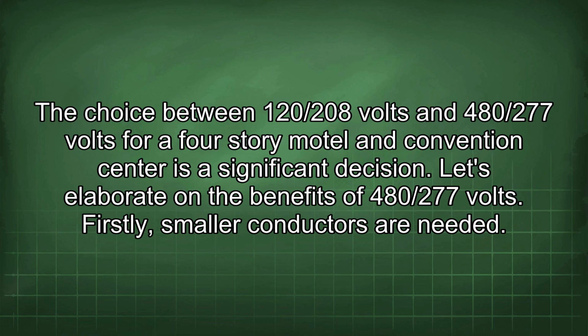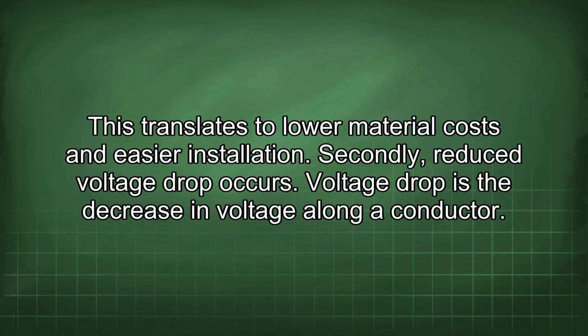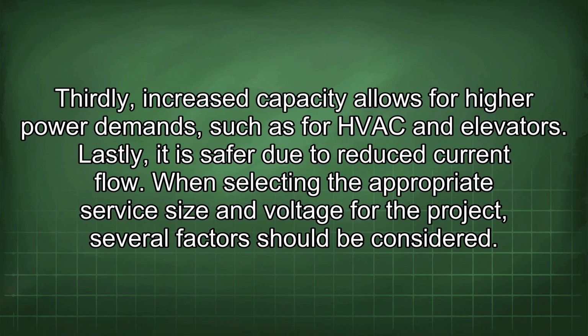Let's elaborate on the benefits of 480/277 volts. Firstly, smaller conductors are needed. This translates to lower material costs and easier installation. Secondly, reduced voltage drop occurs. Voltage drop is the decrease in voltage along a conductor. Thirdly, increased capacity allows for higher power demands, such as for HVAC and elevators. Lastly, it is safer due to reduced current flow.